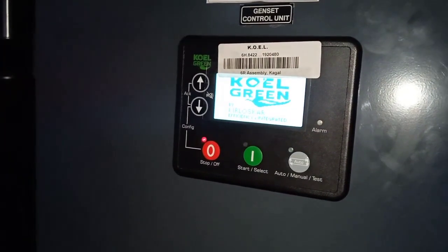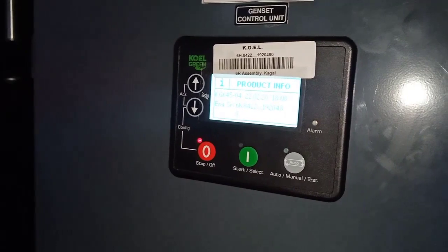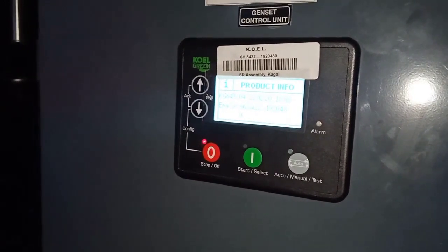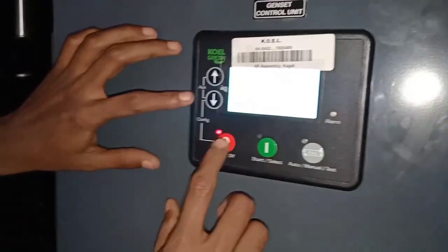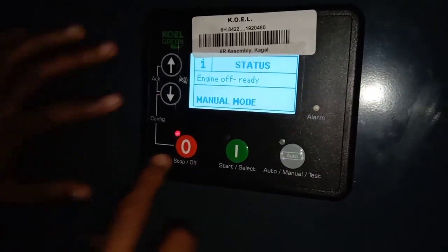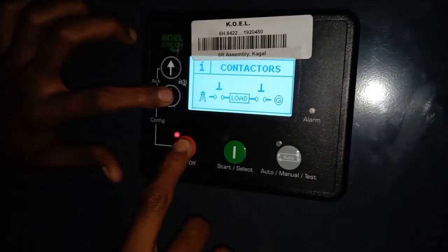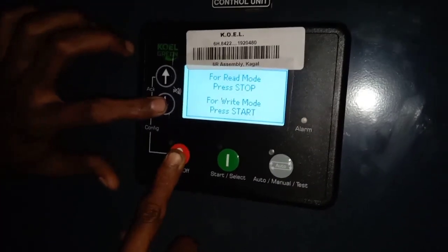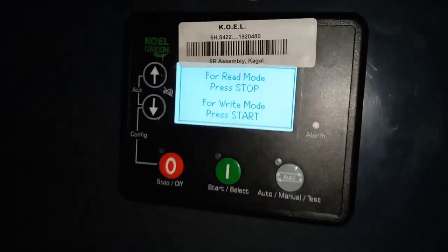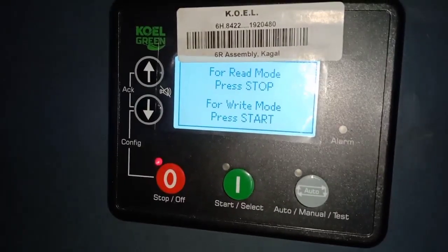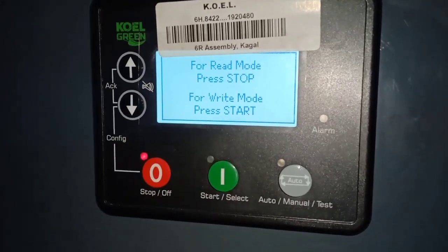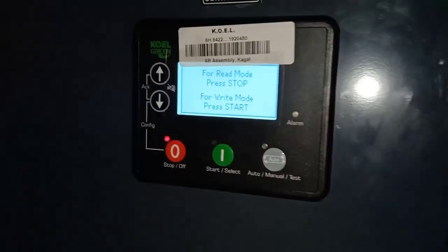First, switch on the control panel and wait for the controller to boot. It may take a few seconds to boot. Once the controller is ready, go to the settings mode, for which you need to long press the down arrow key and the stop button at the same time. Now it shows read mode and write mode. Please select write mode by pressing the start button.